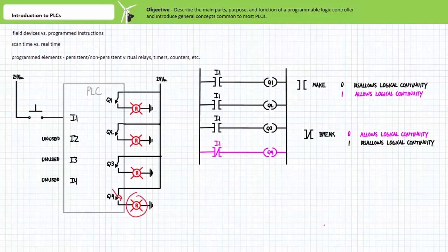Scan time is a sequential reading of a PLC program from top to bottom and then returning to the top. This means if a CPU is currently scanning line four and something on line one changes, the CPU needs to read through the whole program before it starts at rung one again to notice something has changed.